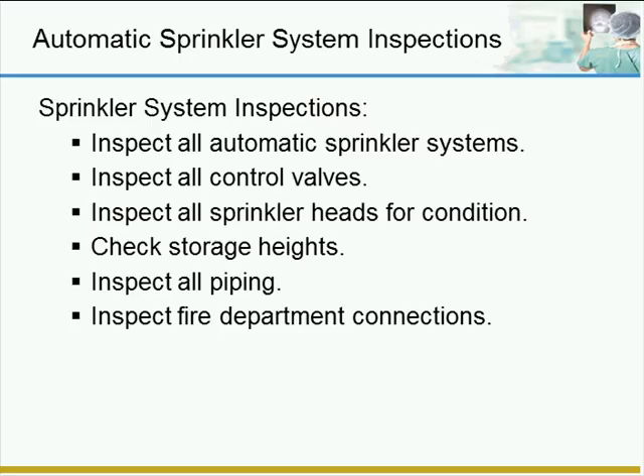Automatic sprinkler inspections can be done by in-house employees to some degree. You should also be aware of storage heights in areas such as linen storage or even record storage. You must maintain at least 18 inches of distance from the top of the storage to the sprinkler heads for the proper sprinkler water spray patterns to occur.